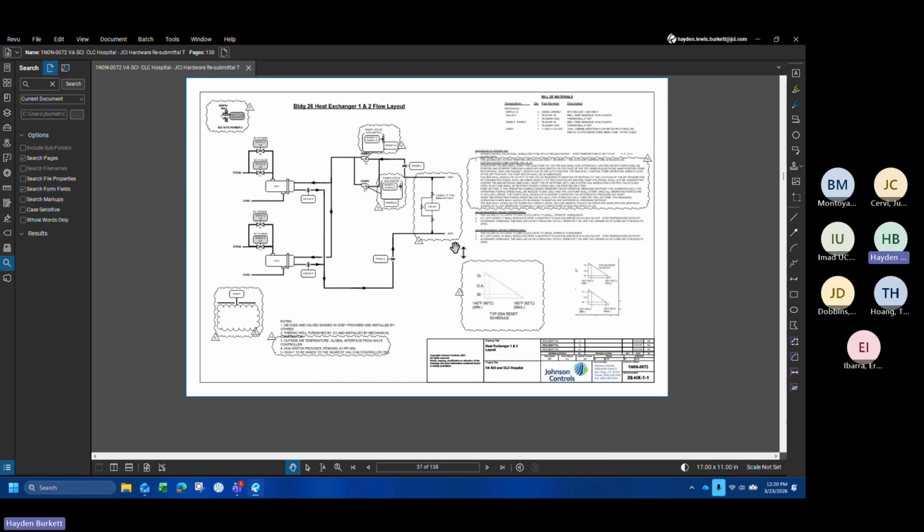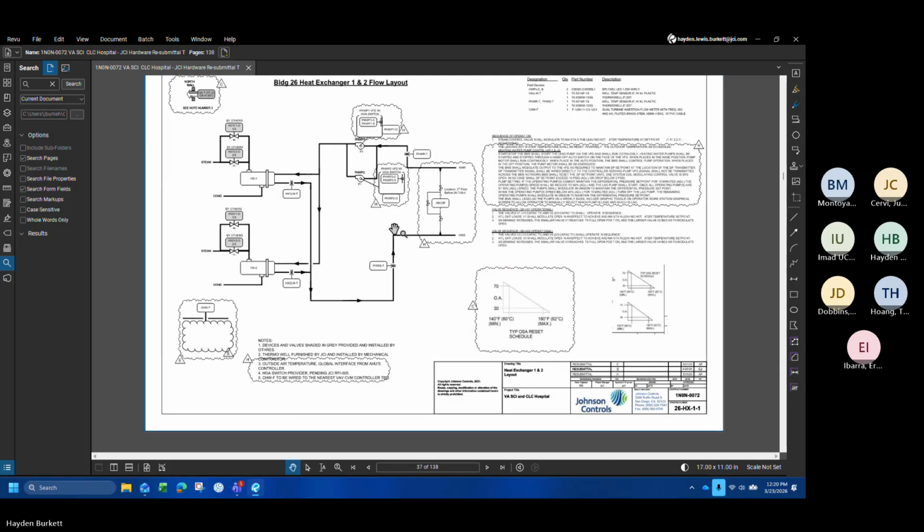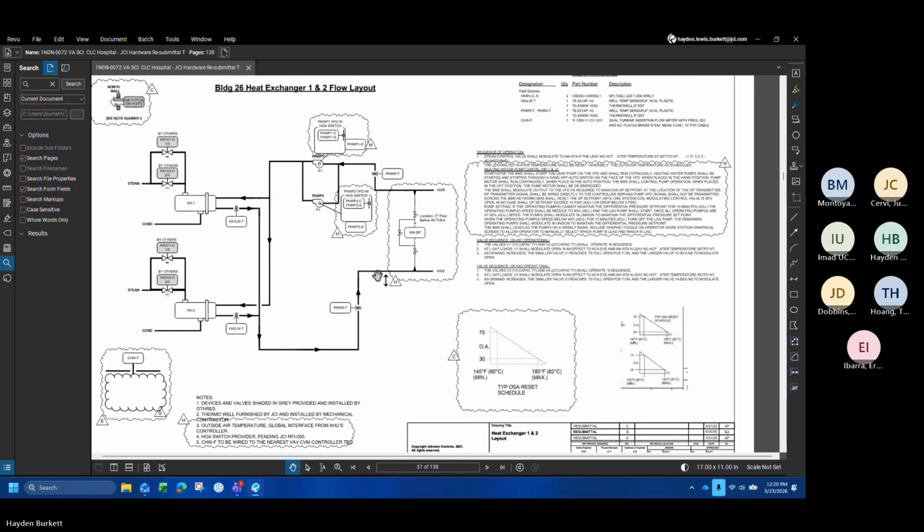Nothing crazy. Cool. Now we're getting into the heat exchanger. A little bit more advanced system. A little bit more going on here. This is basically a pair of heat exchangers. They operate based on demand. So more demand equals basically more steam through the heat exchanger controlled by these actuators. This is an example of an actuator that's been provided by a mechanical, but we control it anyway.